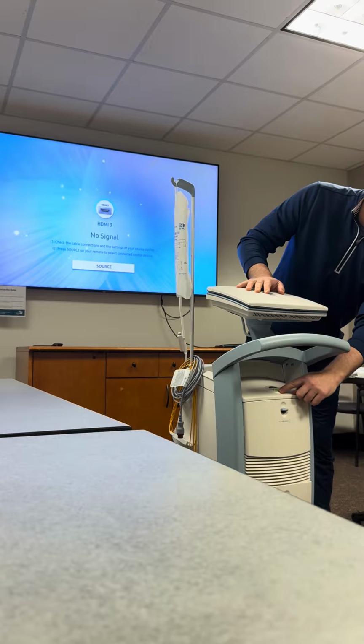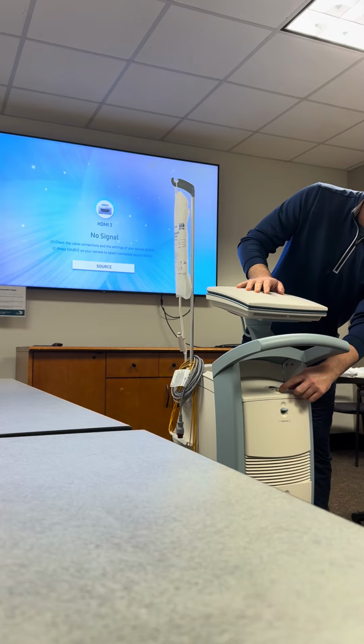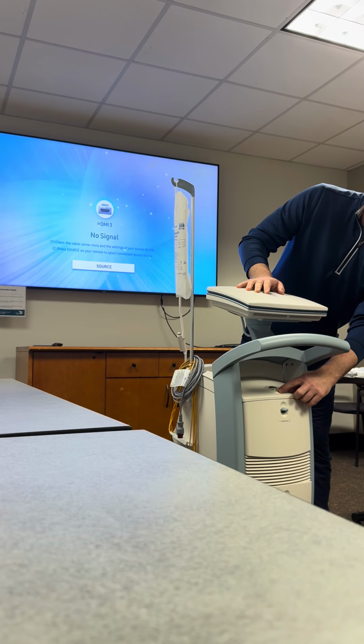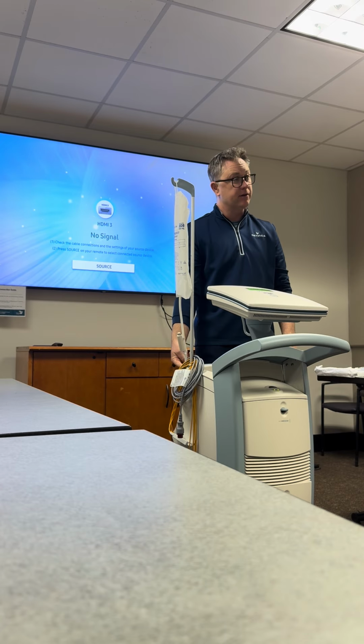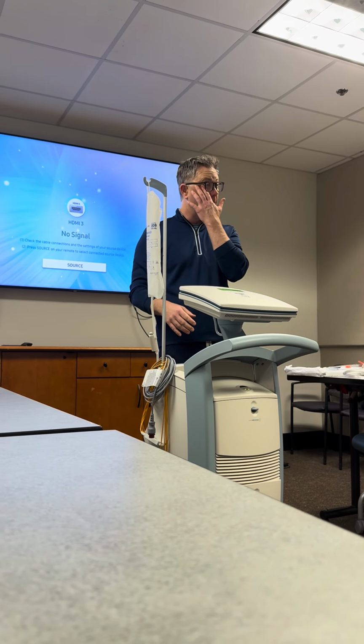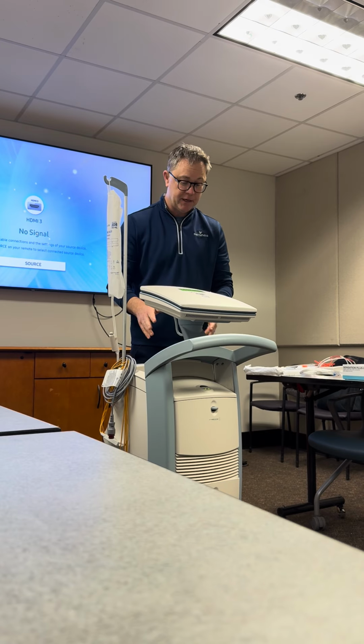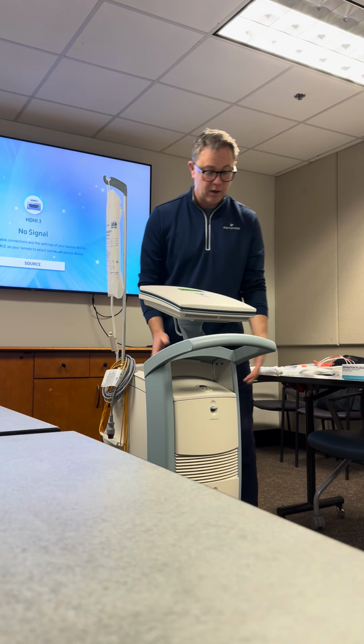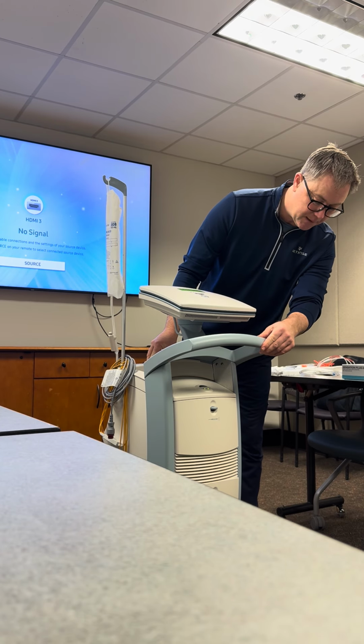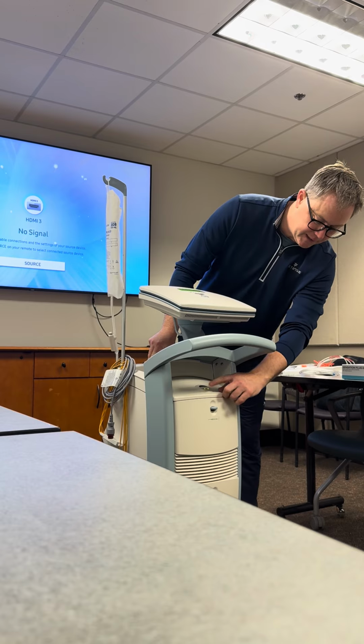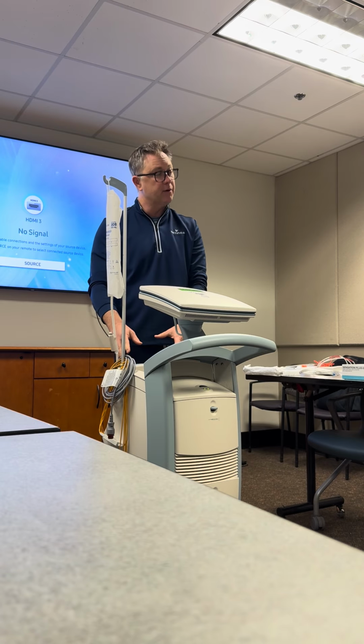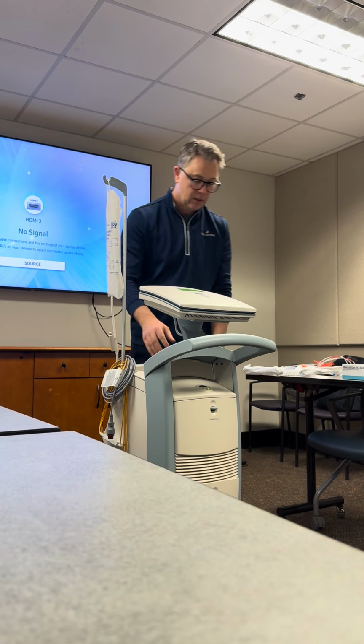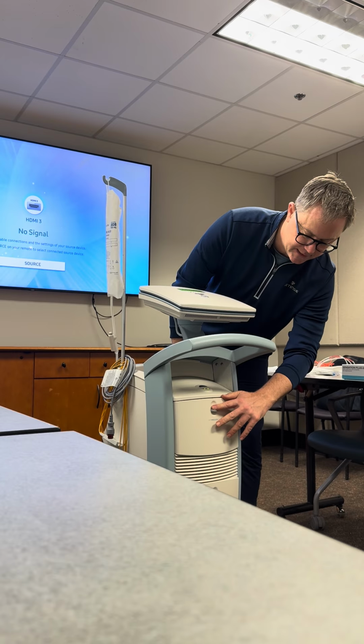This is a battery light indicator. This light is currently charging. It's telling me that my batteries are in the process of charging. We always want to keep our balloon pump plugged in, obviously, when it's on a patient, but especially when it's in storage as well. That's how we keep those batteries charged. If you see it blinking here, it tells you that one of your batteries is in the process of charging. So we'll take a look at those on the back in a second.